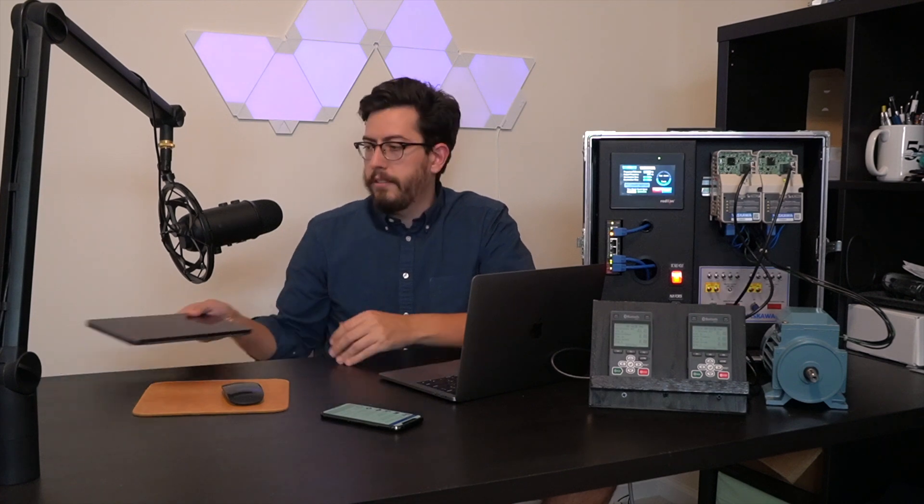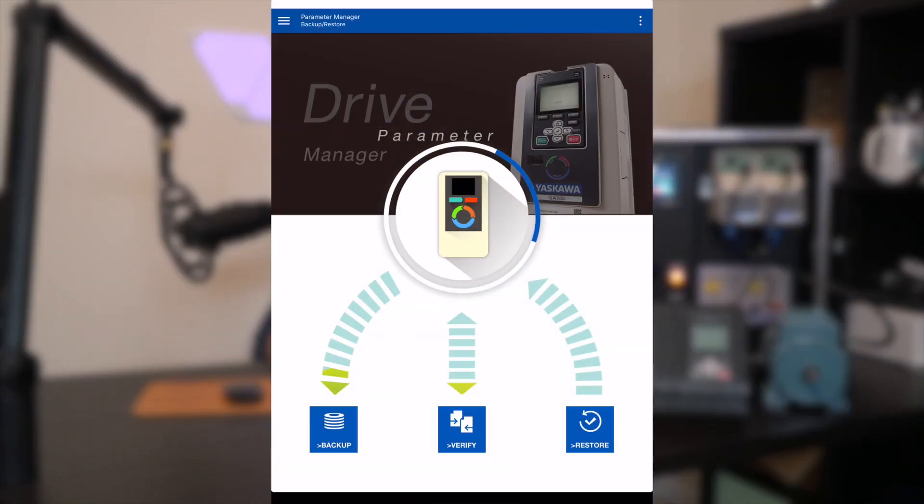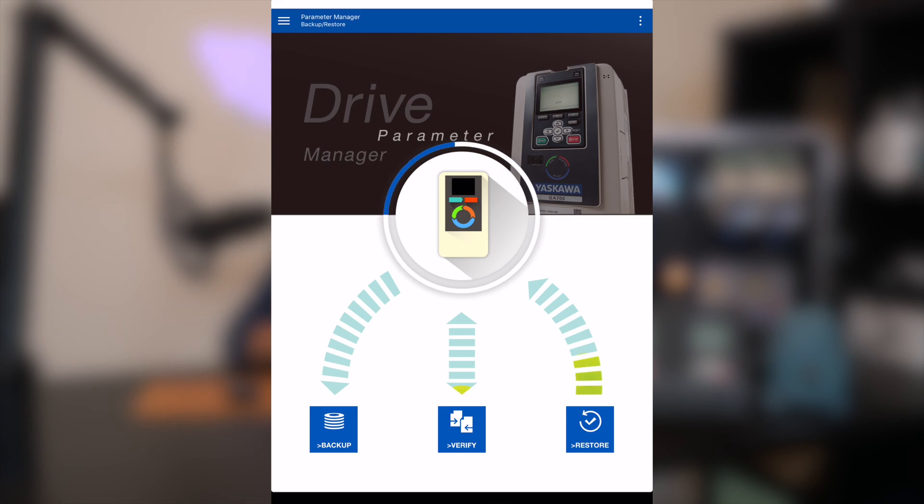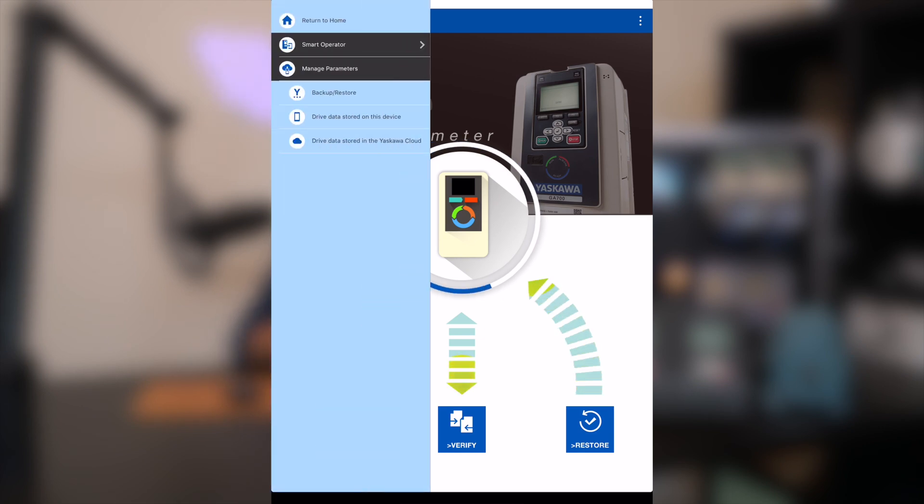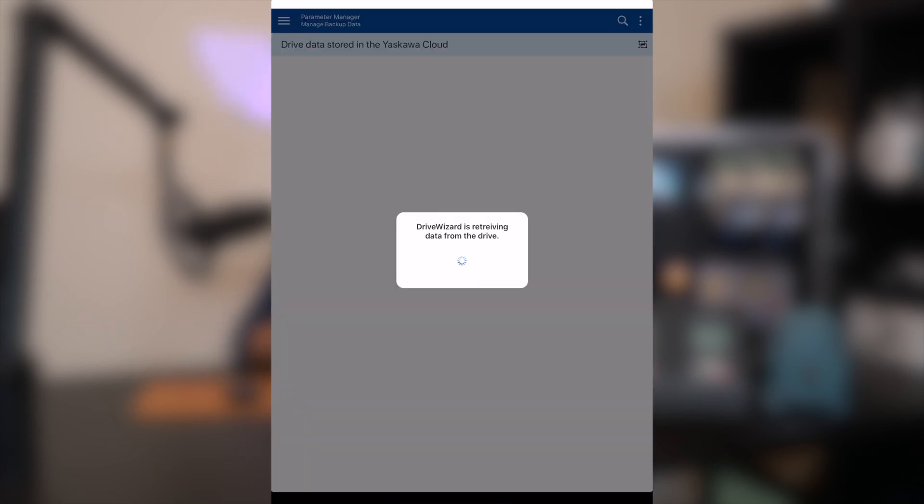Now that I've commissioned my first drive, I can connect to my second drive and quickly upload all the parameters from the backup. To really show the full ability of the cloud, I'm going to connect with a completely different device that's logged into the same account. All I have to do is download a backup from the cloud and then I can restore the parameters from the backup I made on my phone.